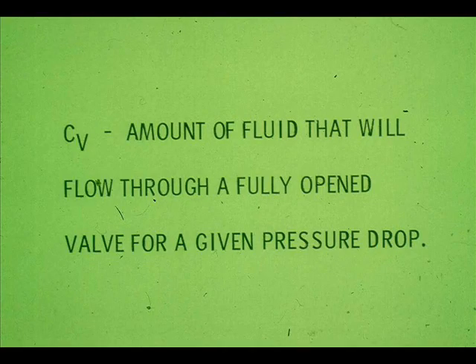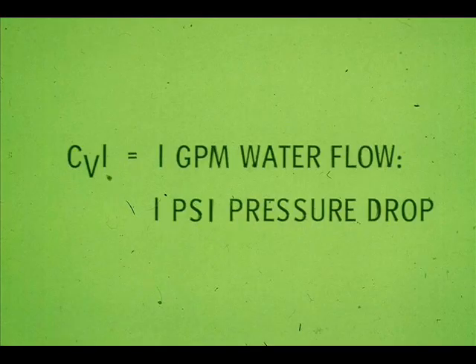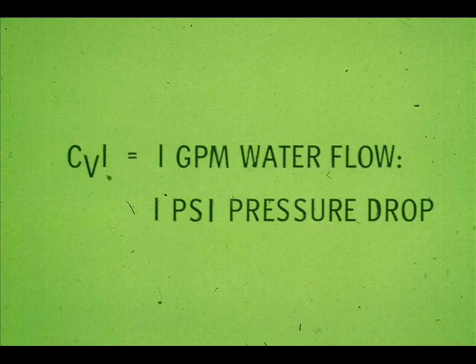Flow coefficient, or Cv, is the yardstick for valve sizing. Cv is the amount of fluid that will flow through a fully open valve for a given pressure drop across the valve. A Cv of one means one gallon per minute of water will flow through a fully opened valve that has a one PSI pressure drop across it.